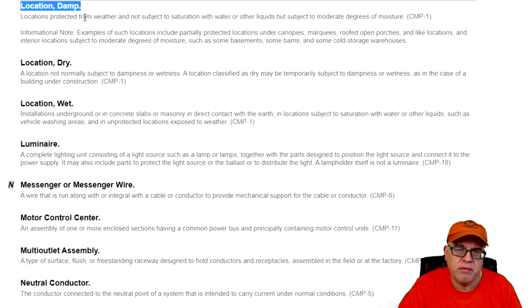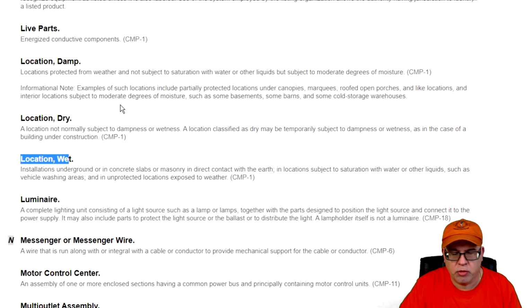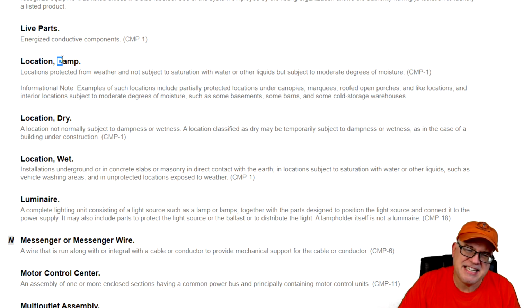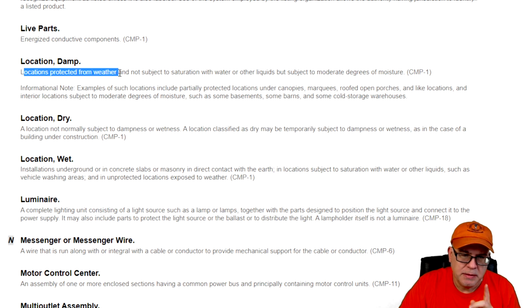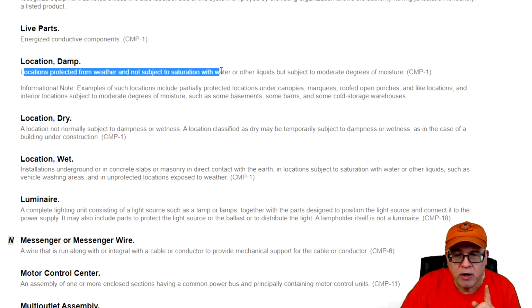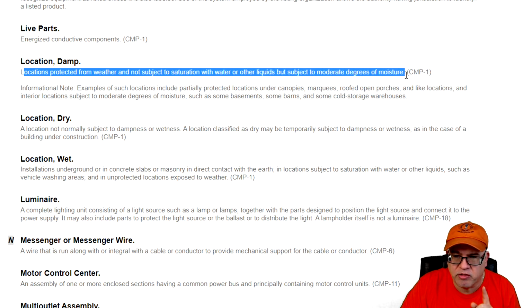Damp location, dry location, wet location. Three different physical types of location. So let's understand these and I'll give you some examples. So what is a damp location? It is locations protected from weather, but not subject to saturation with water or other liquids, but subject to moderate degrees of moisture.